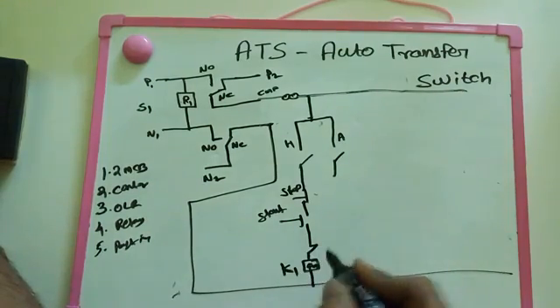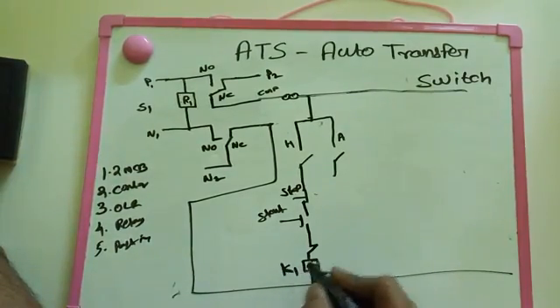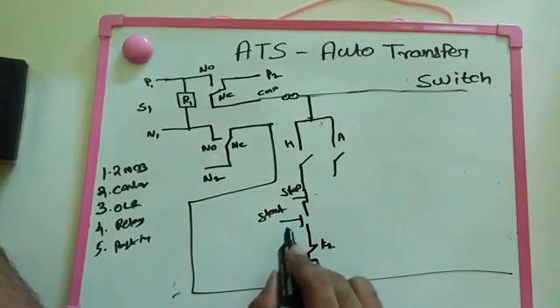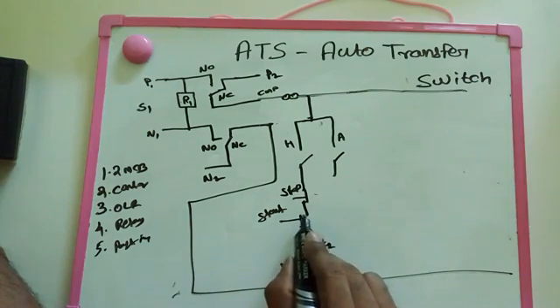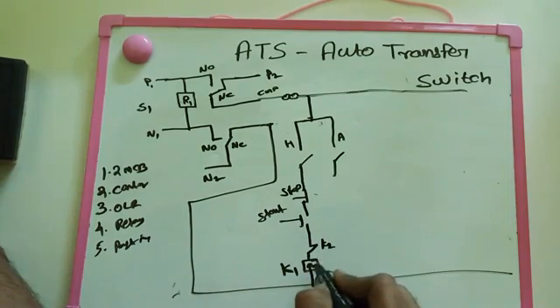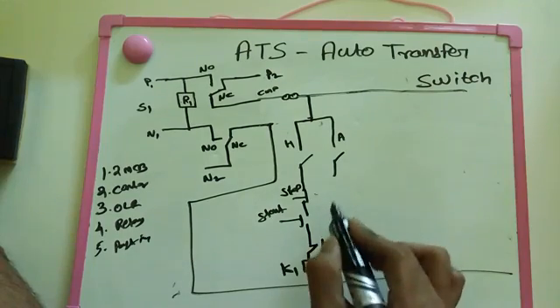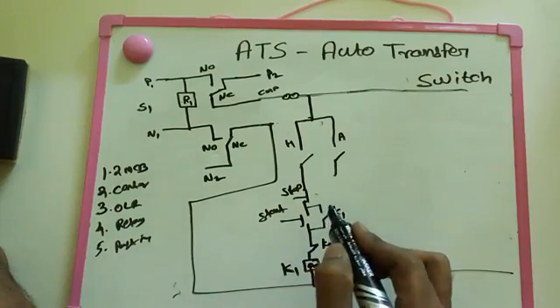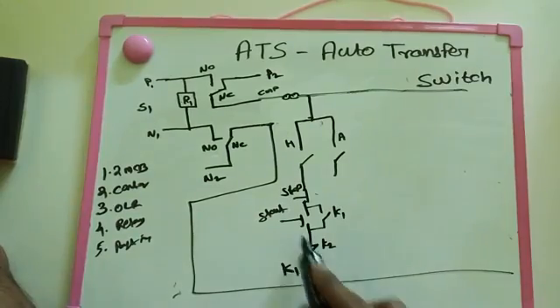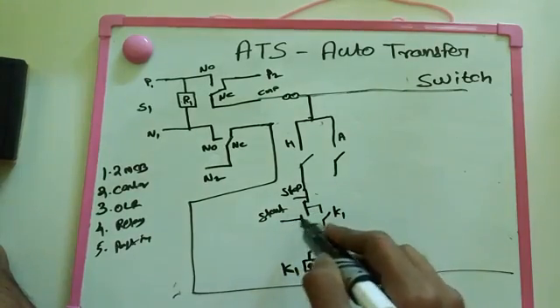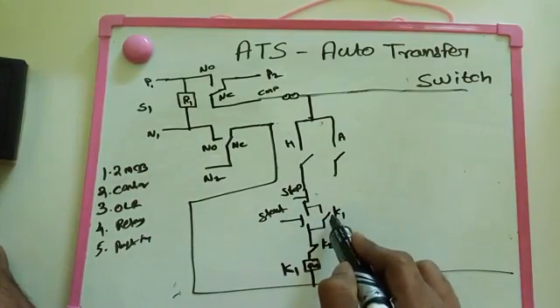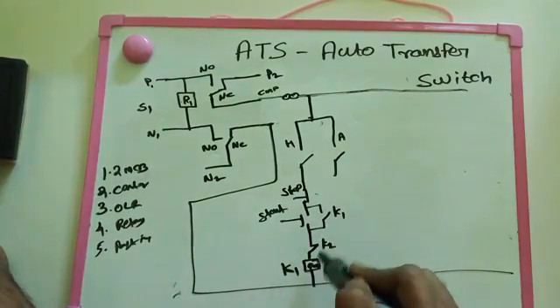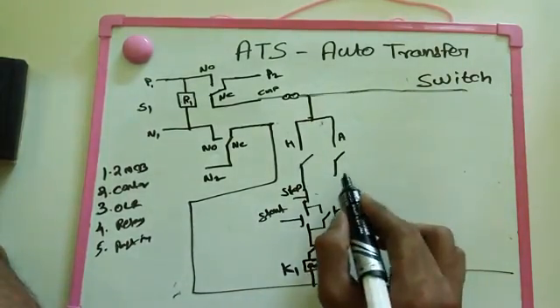This is for K1 - that means supply 1's contactor. I drew it in the power diagram and mentioned it as K1. So this is for main supply, and this one is K2's NC supply. When we press the start push button, this contactor goes to switch on. So that's why we need to make here K1. When we press start, K1 is energized through the start button. After that the start button is released - through the K1 NO contact going to close, so K1 continues to get supply. This is for hand operation.